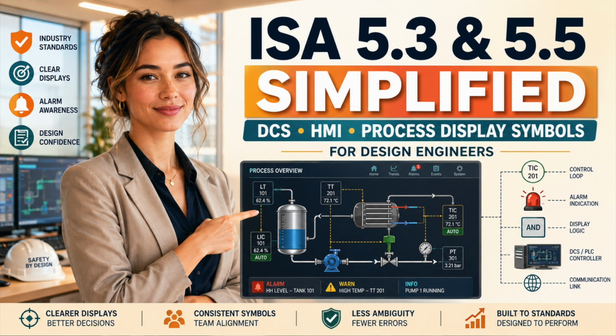Data quality is another area where attractive graphics can become operationally dangerous. A value is not useful merely because it is visible. The operator must know whether it can be trusted. A measurement may be good, bad, uncertain, stale, forced, substituted, simulated, out of range, or calculated from failed inputs.